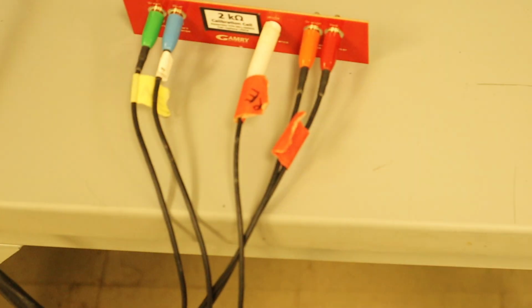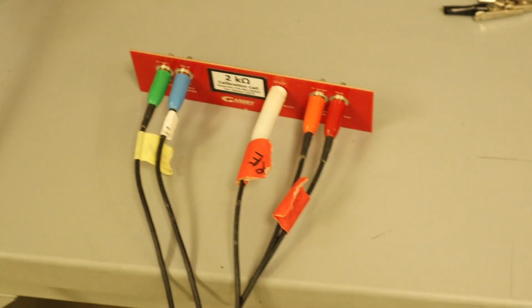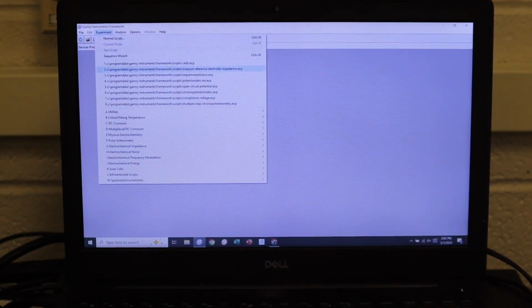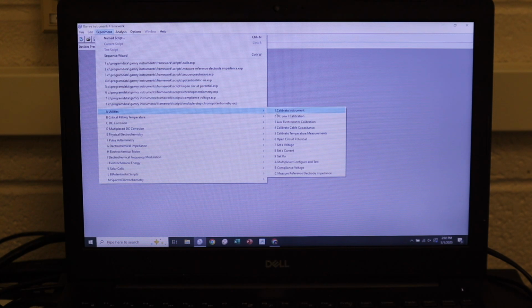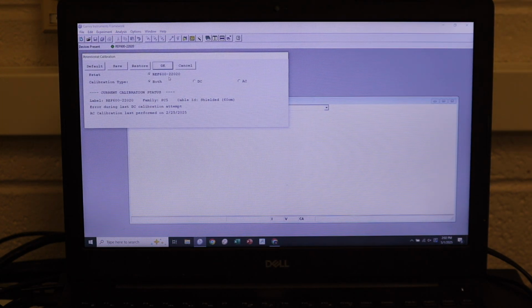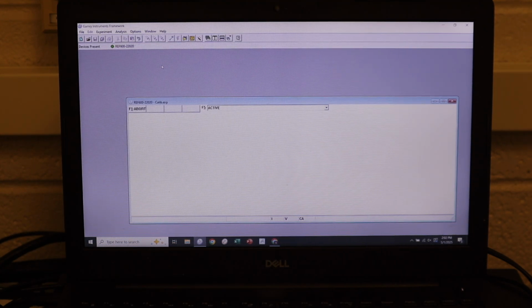Alright. So now we have our calibration cell set up. It's connected to the Gamry, like so. Our wires coming from the Gamry are connected directly to the 2 kilo ohm Gamry calibration cell, and we're looking right at our Gamry software. In our Gamry software, we can now go to Experiment, Utilities, and Calibrate Instrument. It'll ask us if we want to look at this reference electrode, this potentiostat, and if we want to calibrate the AC, the DC, or both types of current. We have it selected to both, so we can go ahead and hit OK.